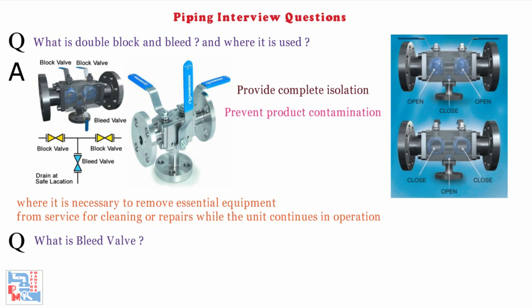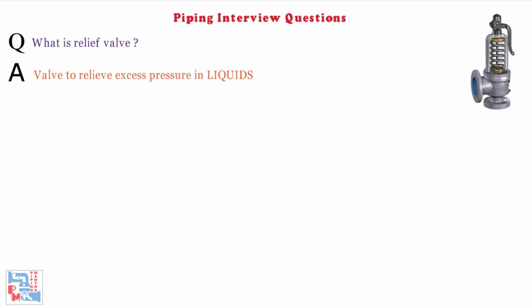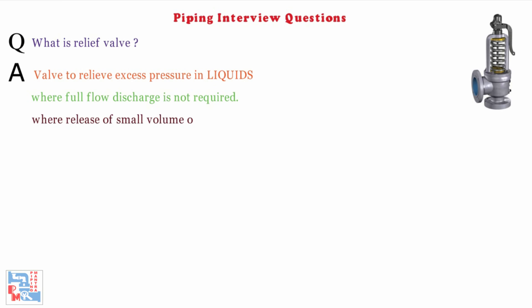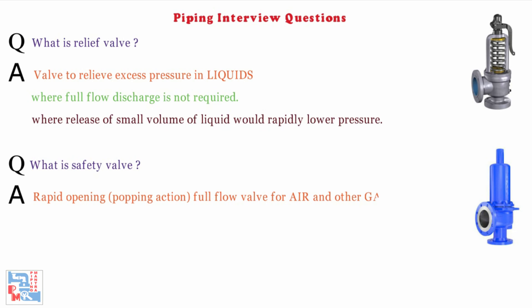Next: What is a bleed valve? A small valve provided for drawing off liquid; in layman's terms we call it a drain valve. Next: What is a relief valve? A valve to relieve excess pressure in liquids in situations where full flow discharge is not required, where release of a small volume of liquid would rapidly lower pressure. Next: What is a safety valve? Rapid opening, popping action, full flow valve for air and other gases. Relief valves are used in liquids whereas safety valves are used in gases and vapours.